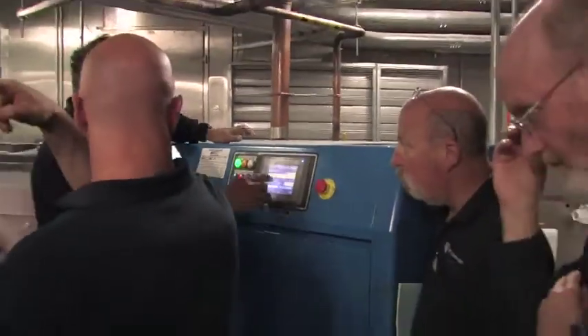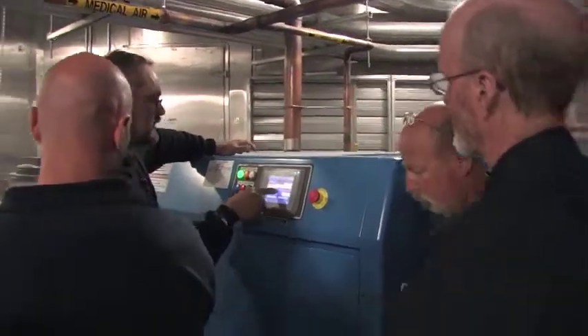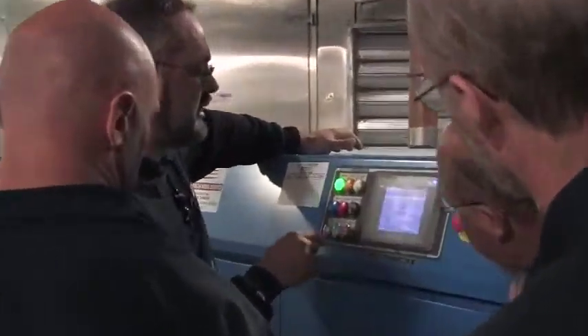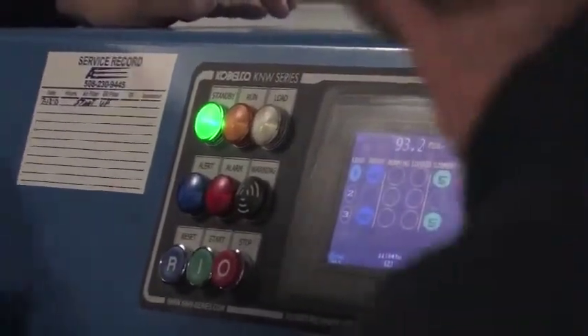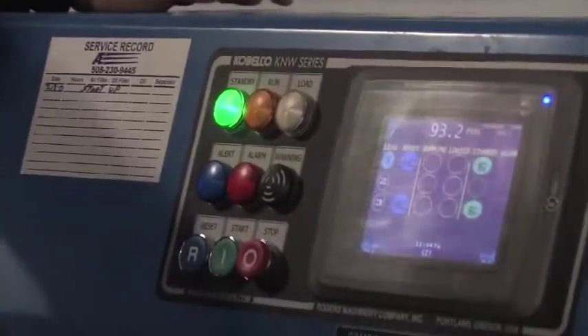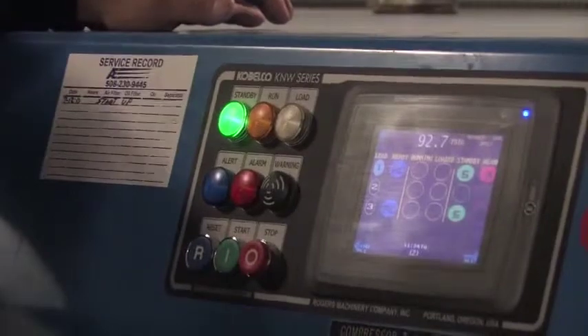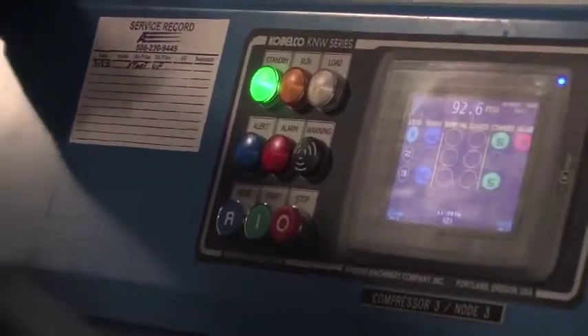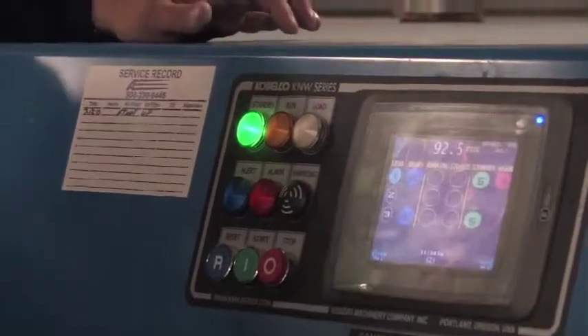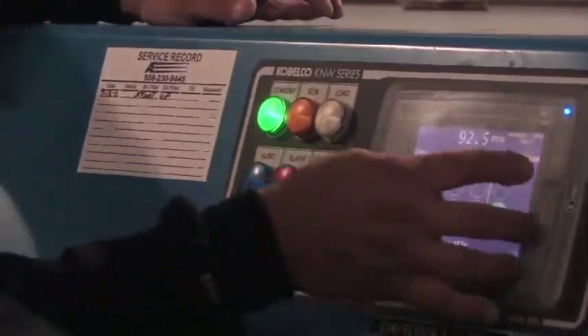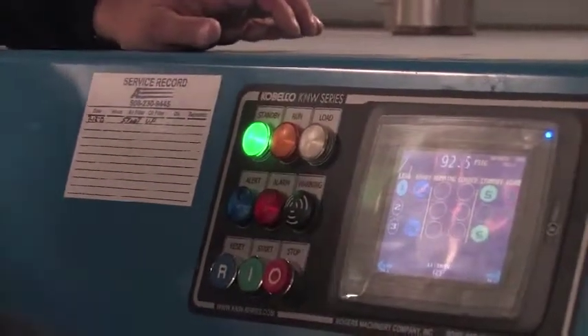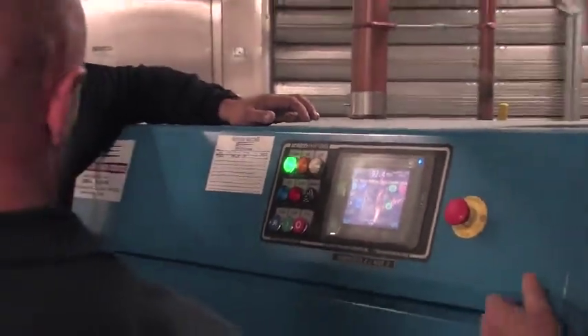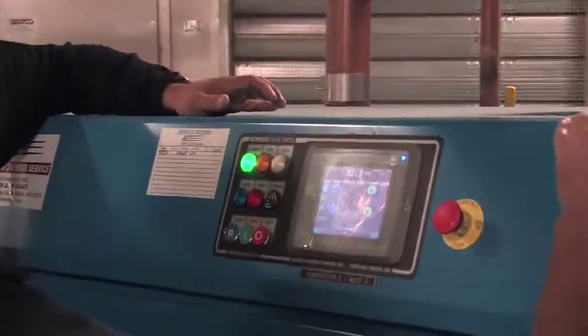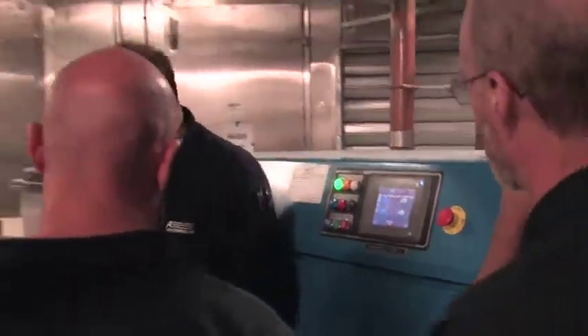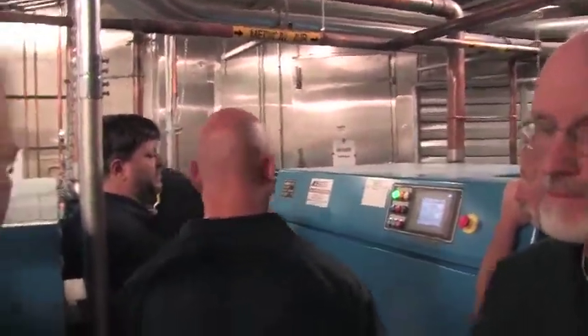Is that an alarm, I'm assuming? Yeah. Now if we look at the sequencer page on this, we will probably find out. Now remember, 2 was the lead before, but we turned this one off and took it out of the sequence. So since this was out of the sequence, it rotated pumps. Why is one an alarm? One is not an alarm. That's an alert. One itself is not an alarm. That's the sequencer getting an alarm. Master's going to give all the alarms. We have not acknowledged that this thing was down before. In other words, because we disconnected this thing, killed the power, and brought it back, if we go over there, it's going to say something about that. We get acknowledged. Yep.